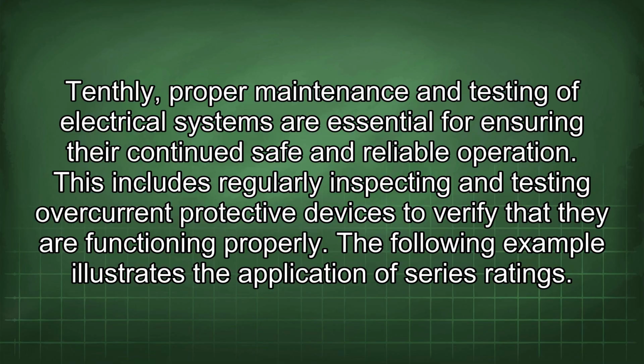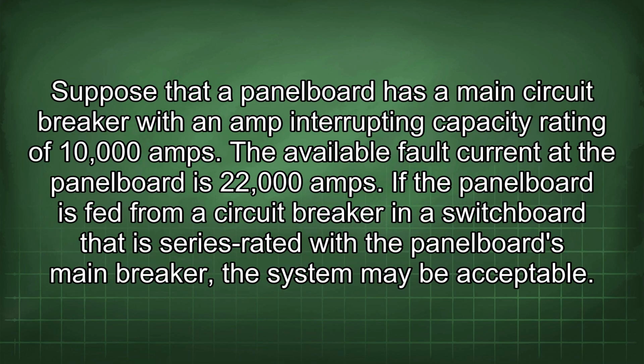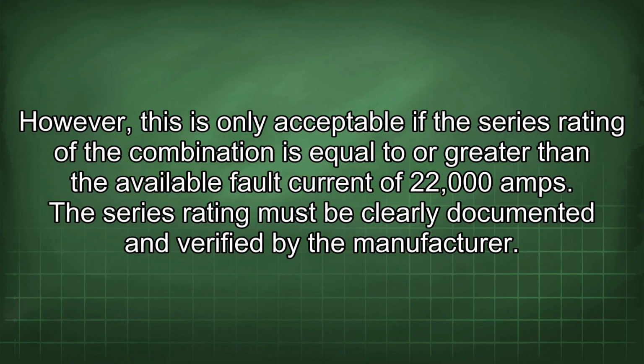The following example illustrates the application of series ratings. Suppose that a panel board has a main circuit breaker with an amp interrupting capacity rating of 10,000 amps. The available fault current at the panel board is 22,000 amps. If the panel board is fed from a circuit breaker in a switchboard that is series rated with the panel board's main breaker, the system may be acceptable. However, this is only acceptable if the series rating of the combination is equal to or greater than the available fault current of 22,000 amps.